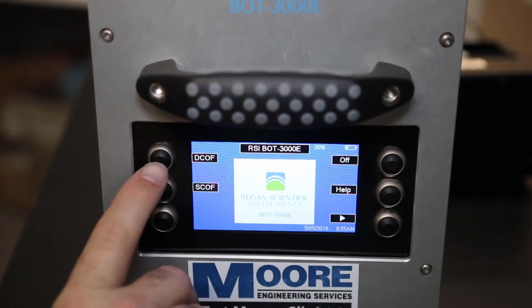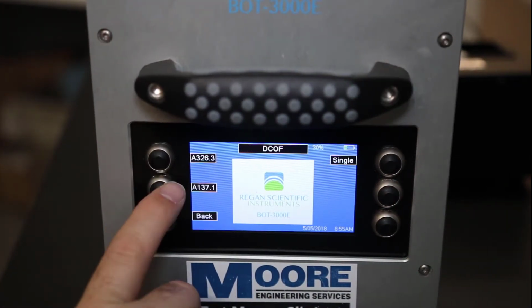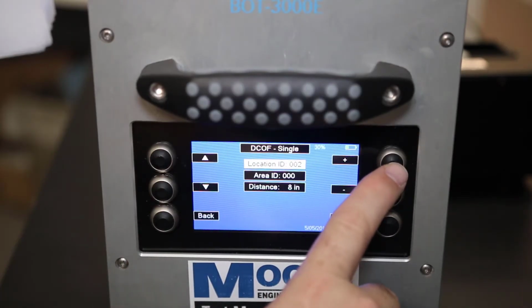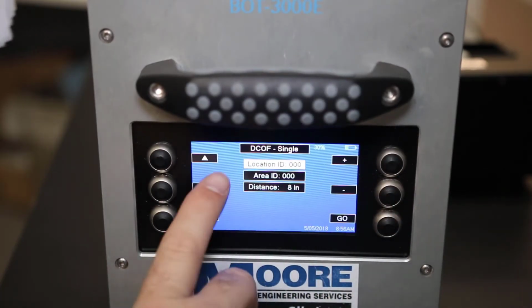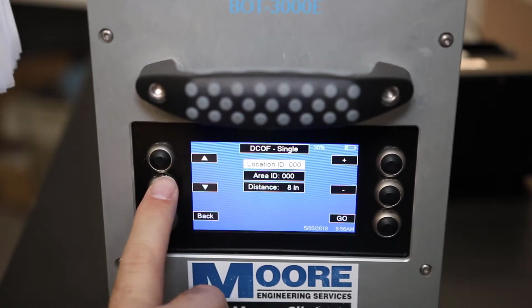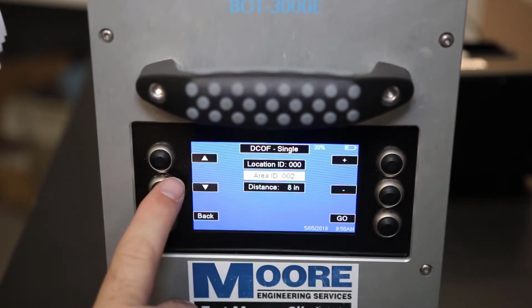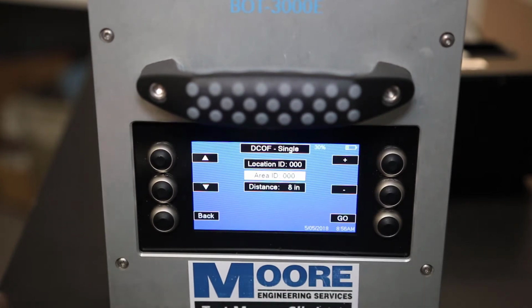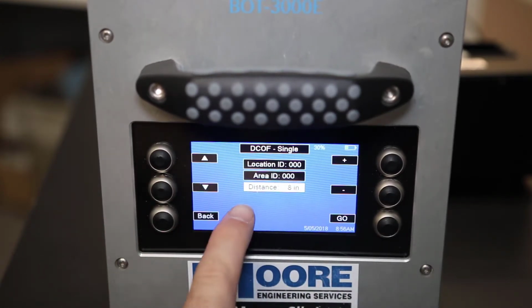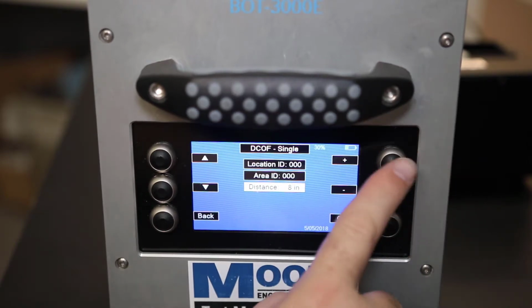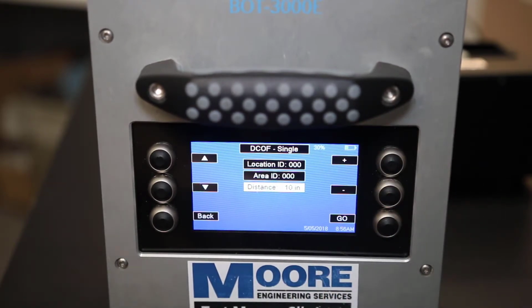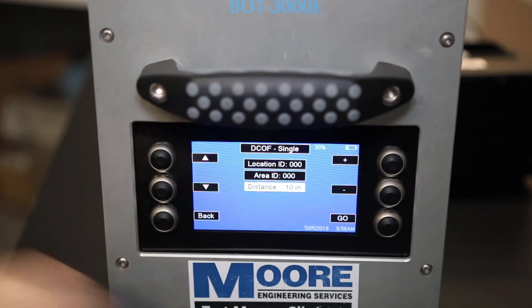For measurements of different locations within an area, you use the buttons next to the plus and minus options, increasing or decreasing the location IDs. The same goes for your area ID numbers. You can also change the distance at which the test is run. Standard distance for the ANSI A326.3 standard is 10 inches, but in circumstances where areas are tight, you can use lower test run lengths, as long as they are indicated within your report.